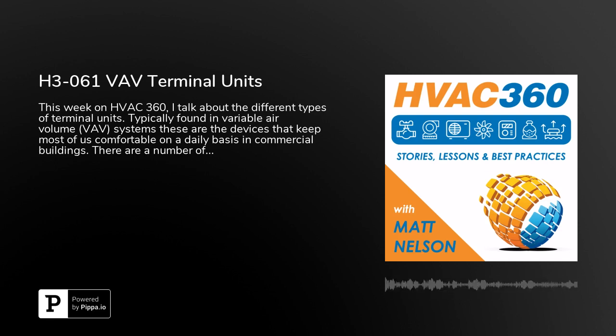Then you had bypasses and dump boxes. I've seen them in a few cases where they've been used more at a terminal. More often than not, in situations where you have a constant volume air handling unit, you'd have it more as a system bypass. That's where I've seen them more often used. These bypass boxes are sometimes called dump boxes. They're kind of like three-way valves for air systems. So instead of transmitting the air down the ductwork, it just diverts it out a side port and dumps it in the plenum space to go back to the air handling unit. A lot more times I've seen those on VAV units, but nowadays with VFD drives becoming more the standard on these rooftop units or small air handling units, these things are becoming more of a thing of the past.